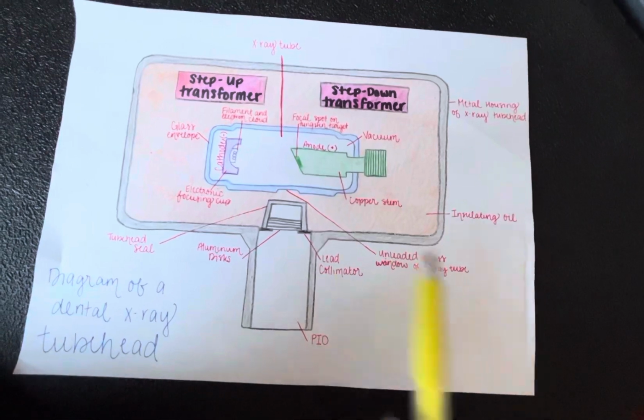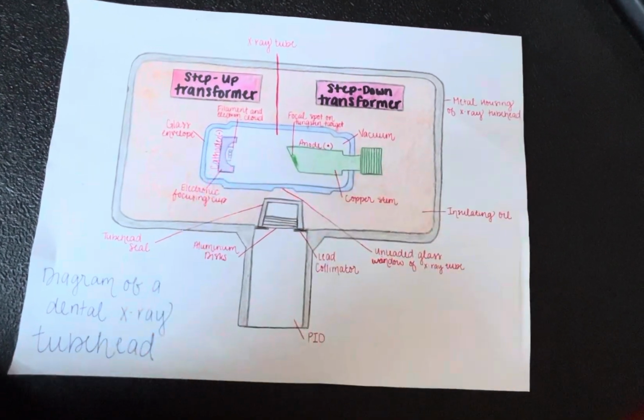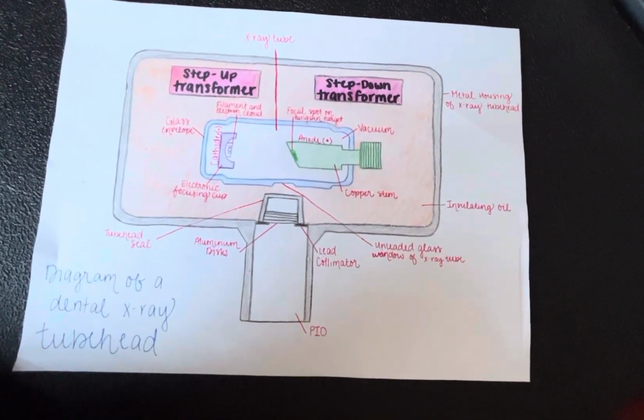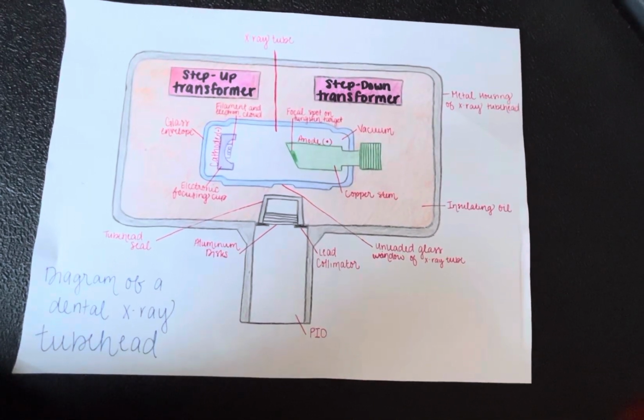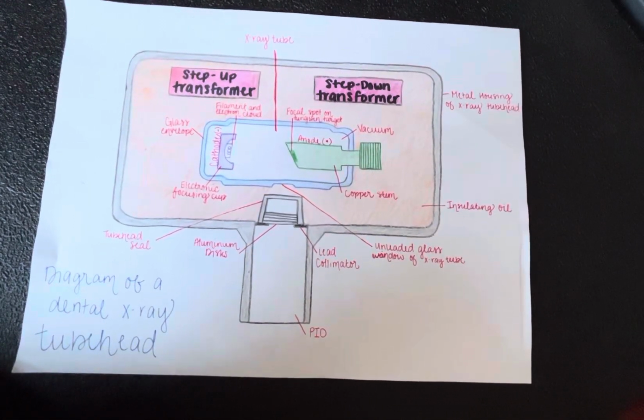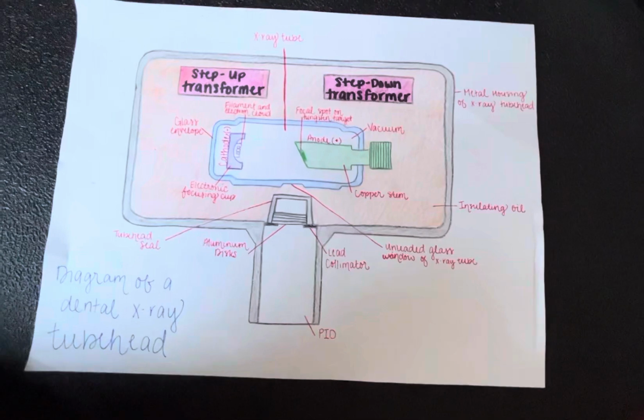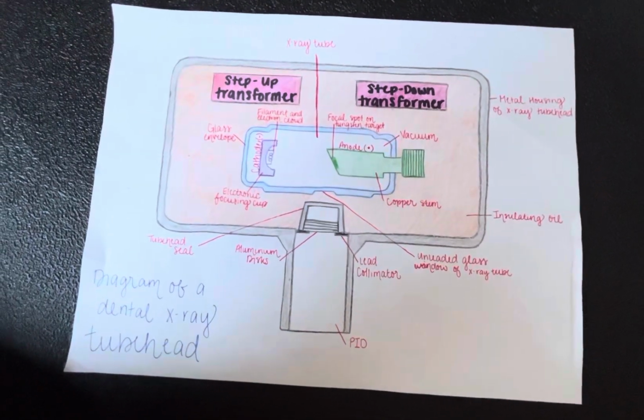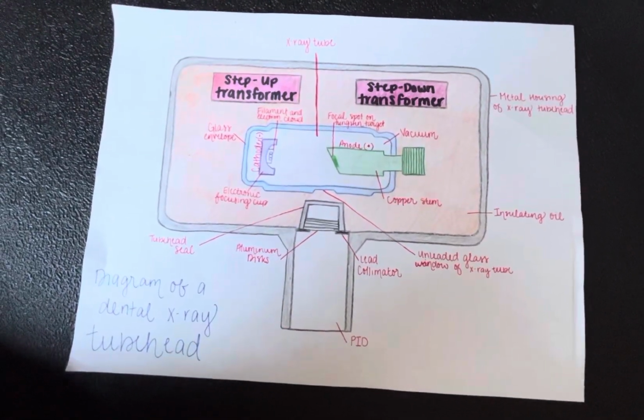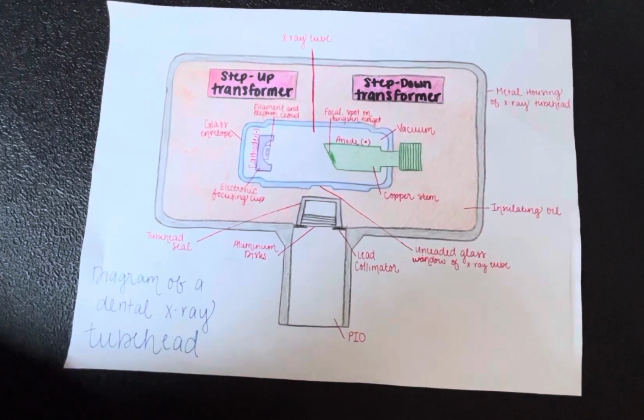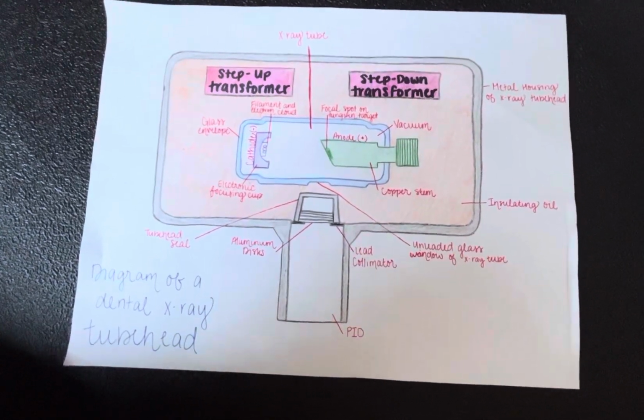Next is the X-ray tube, right here. It's known as the heart of the X-ray generating system. It is critical to the production of X-rays. It is a glass vacuum tube that contains no air. It is about 1 inch in diameter, and it contains the leaded glass housing, cathode, and anode. We'll talk more about this in a minute.